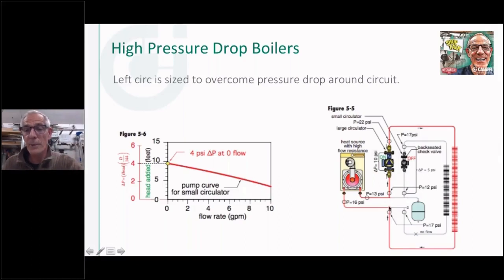So we're getting around here, and we come back, we get down to the end of the road here, and we drop down to 17 PSI. So we went from this 22 at the discharge, through the heat emitters, through the circuit, down to 17 PSI. Now, this smaller circulator on a smaller distribution over here is off right now. So I've got 17 PSI here, I've got 17 PSI going around the loop, and I've got 17 PSI against this check valve on the discharge side of that circulator. So I'm backseating that check valve with that delta P that's being developed by this big pump.